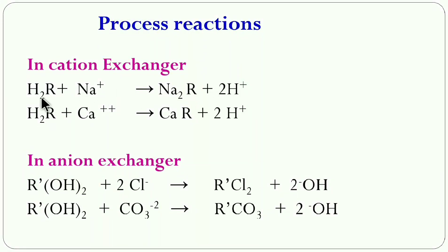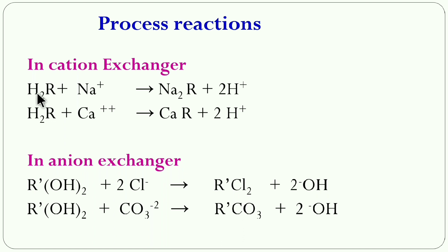In terms of reactions: cation exchanger resin H₂R reacts with Na⁺ ions to form Na₂R, releasing H⁺ ions into water. Similarly, H₂R reacts with Ca²⁺ ions to form CaR, releasing H⁺ ions. These reactions show that the resin captures heavy metal and other cations while releasing H⁺ ions — applicable to any cation present in water, whether or not it is responsible for hardness.